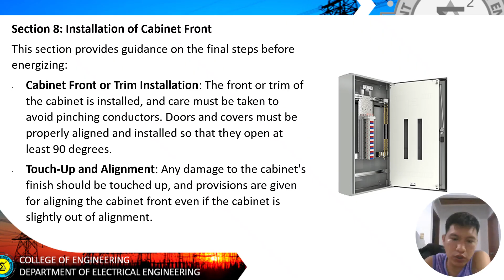Energizing equipment - the qualified personnel should do the energizing. If you're the engineer who worked on it, you are the qualified personnel to energize that one. And no load on panel board: the panel board should be energized without any load, and all downstream devices should be turned off. So we don't put load first, we energize first, and then follow up with the load.